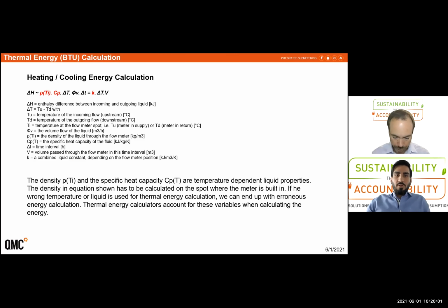I wanted to go over thermal energy calculation, as some of the larger energy-consuming systems within buildings are the central hydronic HVAC system and the domestic hot water system. Whether it's used for billing, rate setting, or energy management, accurate metering and data is a necessity. In the equation shown here, density and specific heat capacity are dependent factors on the temperature where the measurement is taken.